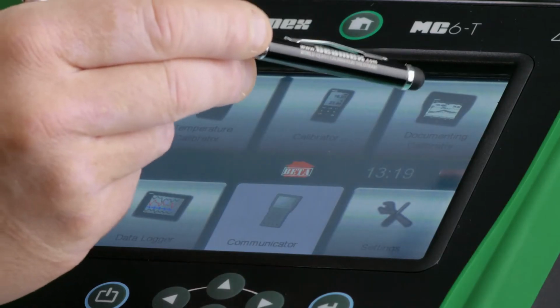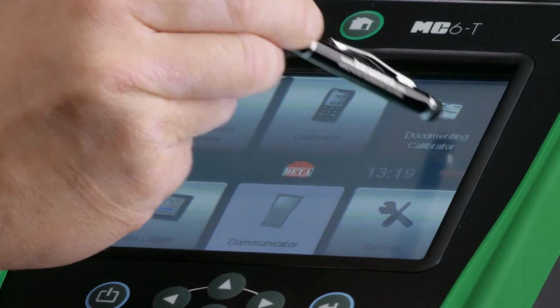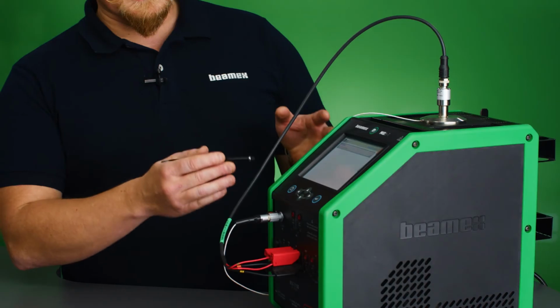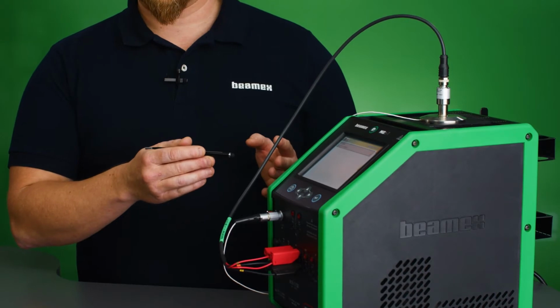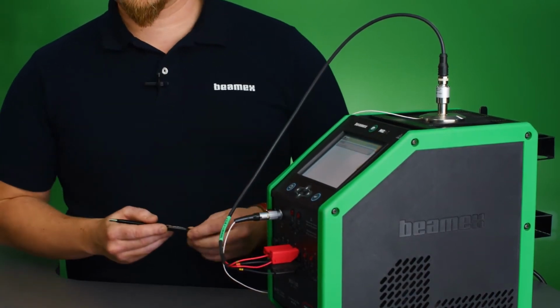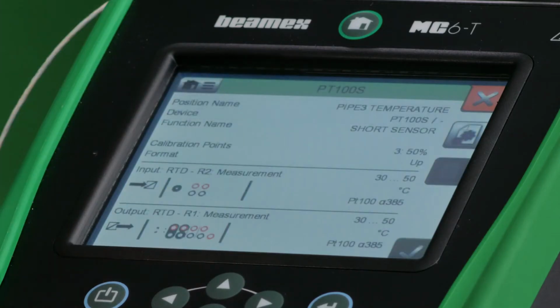Let's calibrate this short sensor. To do so, I will need to go to the Documenting Calibrator mode on the MC6-T, and I'll find it here in the upper right corner. I can send my instrument to the calibrator either by generating it first in calibration management software such as CMX or Logical, or I can make it manually here on the MC6-T. I have already sent it from CMX, so I can start my calibration.